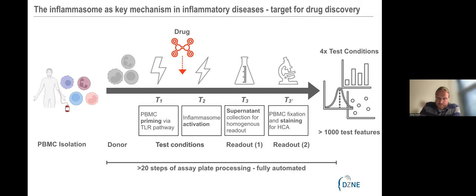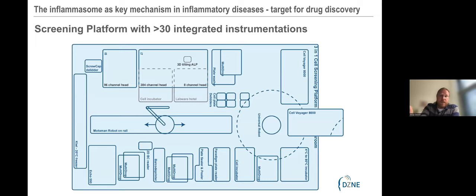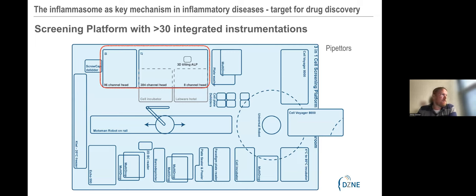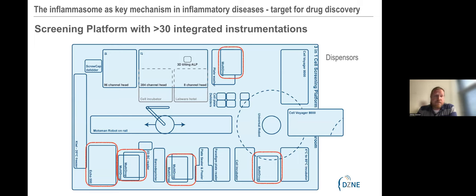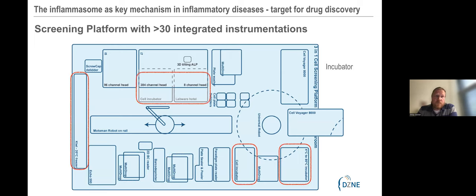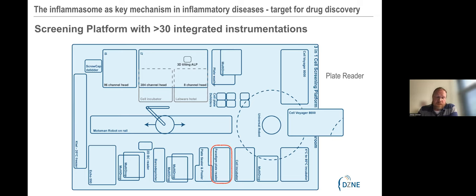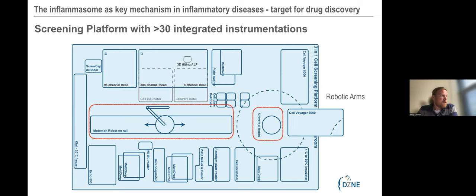In our lab, we have a special environment where we fully automate more than 20 steps of sample processing quite reliably. From each well we extract more than 1000 test features that we can analyze. We have a special screening platform — a very complex one — with different pipetters integrated: 96-channel head, 384-channel head, 8-channel heads, i5 and i7. We have various dispensers, an Echo integrated for compound dispensing, all the incubators needed, a plate reader for homogeneous readouts, and state-of-the-art high content screening imagers — the Cell Voyager 8000.